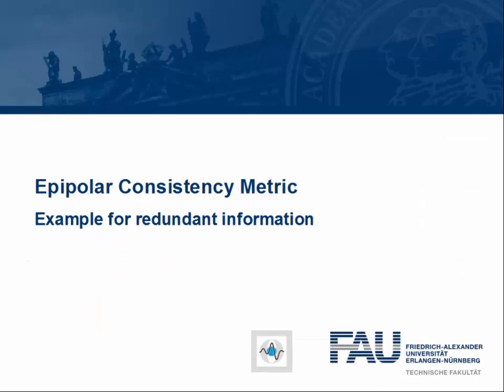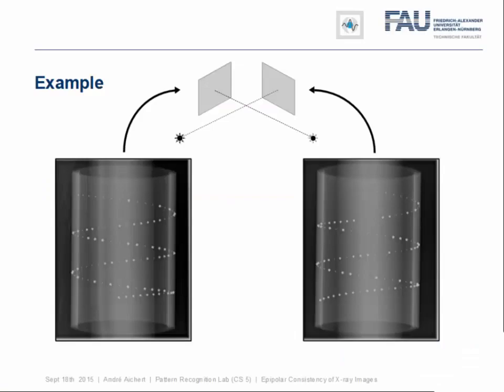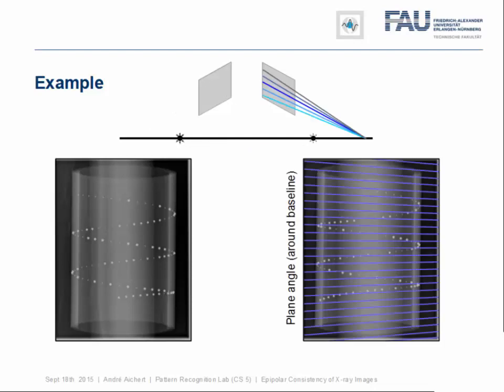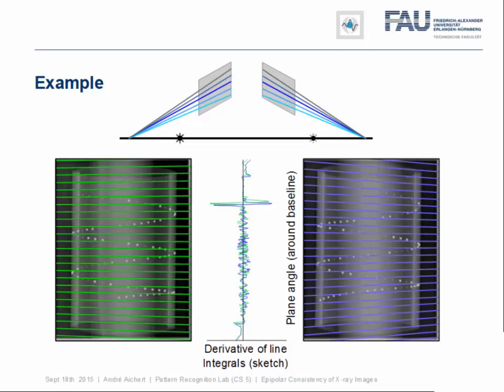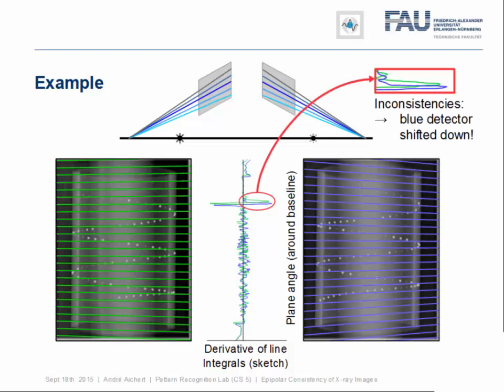We will now apply what we have observed to two sets of example images. The first is a calibration phantom, which is a plastic cylinder with metal beads embedded into it. We take two images at about a 90 degree angle. We can then extract the epipolar geometry, get the baseline, and get the epipolar lines in the first image. We then integrate in the direction of the epipolar lines and take the derivative in the orthogonal direction. We get the following signal. We can then do the same thing for the other view. We get the green signal. You can see that the signals are correlating well. However, if you look closely, there is some inconsistency between the two. In fact, we could improve consistency by shifting the blue detector up just a little bit.